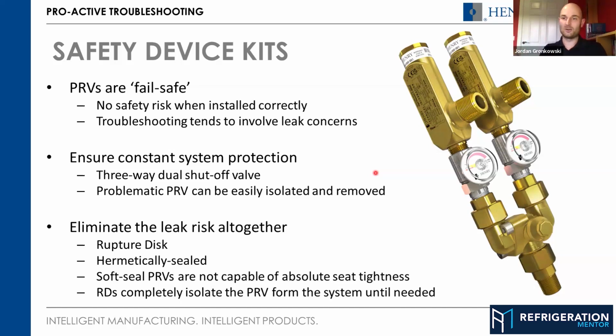And then 10% over your set pressure is the point at which the valve has to be fully open by then. Usually the valve's fully open before that. Ours typically get fully open about 5 or 6% above set pressure. So it'll start to bubble within your 3%, and then at some point, around 5 or 6%, it'll go bang, and it'll be fully open.